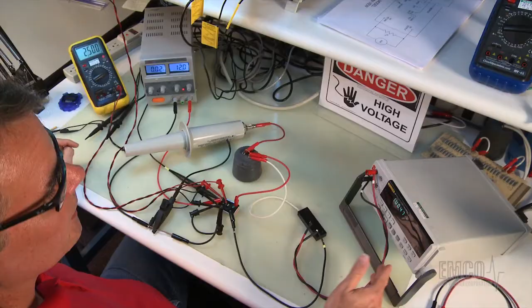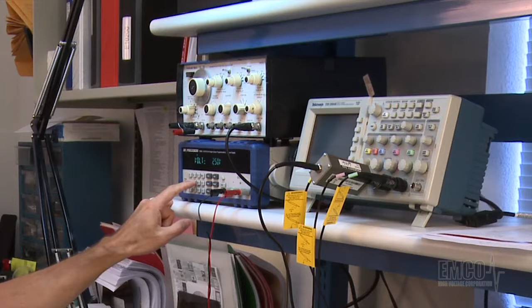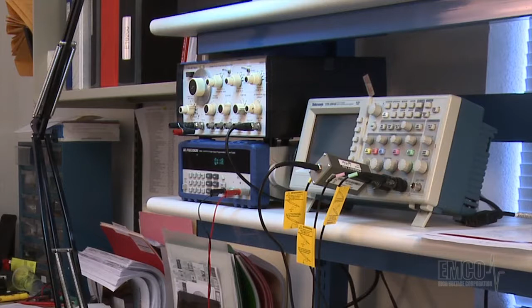So I'll set my programming voltage to 2.5 volts, and we can see we get a corresponding very close to the nominal 1,000 volts with 2.5 volts at the programming voltage. And again, the monitor voltage tracks accordingly. So finally I'll go ahead and set the output voltage to full scale. So with that, again on the CA20P, that would be 5 volts. I'll set my programming voltage to 5 volts, and now we have an output voltage in range for the nominal output of the unit. And here the calibration of the oscilloscope probe is accurate.